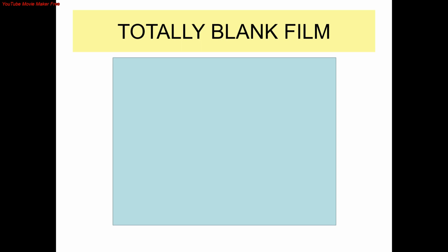Then the next is totally blank film. It is due to non-exposure but development of the film. Second reason is film placed in fixer first, and third reason, film in fixer for a very long time.